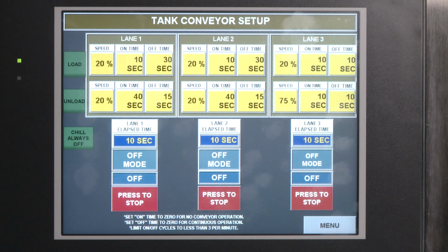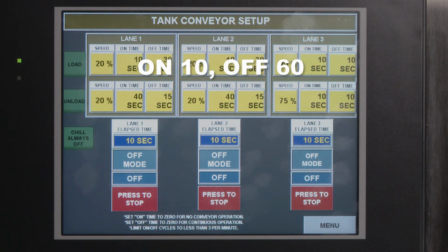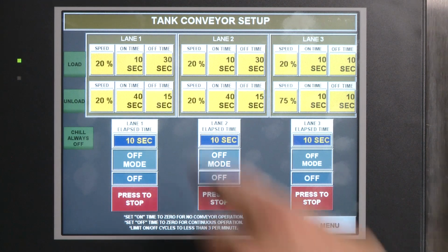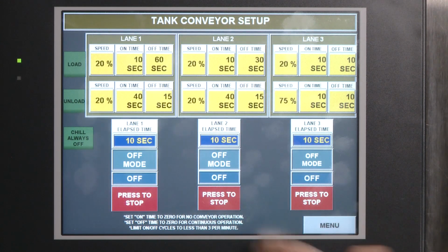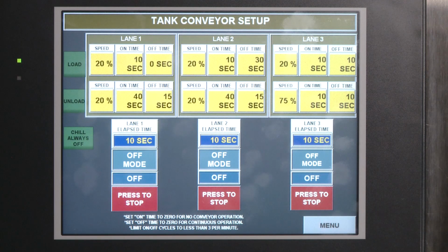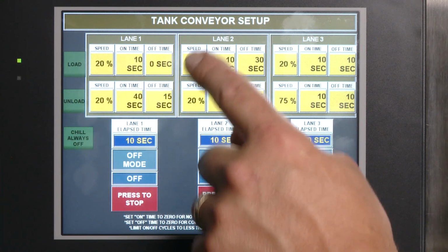The conveyor off time defines how long the conveyors are off in the timed mode. The conveyor on time defines how long the conveyors run. For example, if the on period is 10 seconds and the off time is 60 seconds, the conveyor will run 10 seconds and shut off for 60 seconds. Setting the on time to 0 turns the conveyor off. Setting the off time to 0 allows the conveyor to run continuously. The conveyor speed is how fast the conveyor will run. It may be set between 1 and 100%.